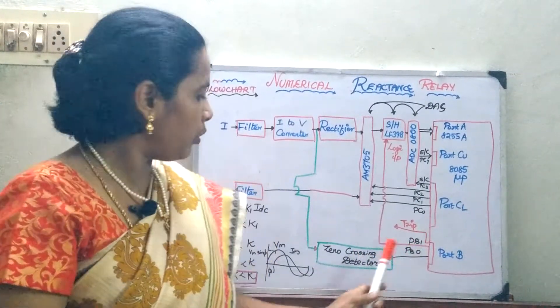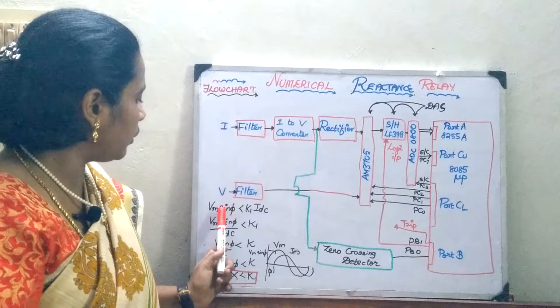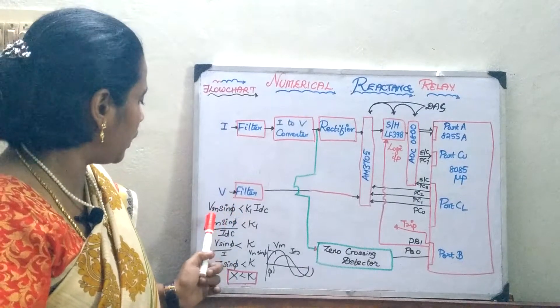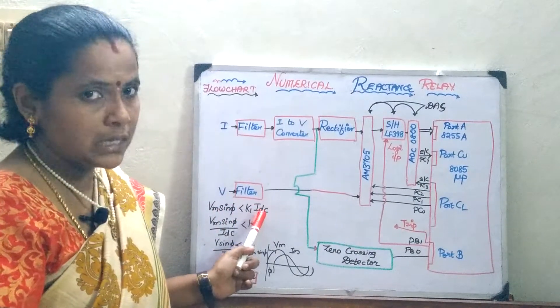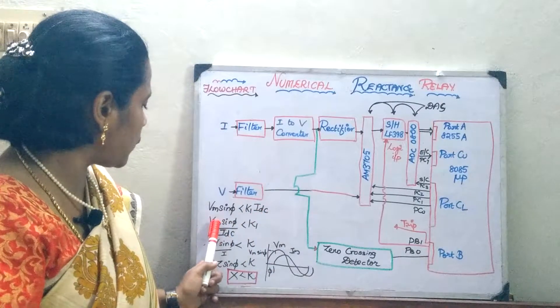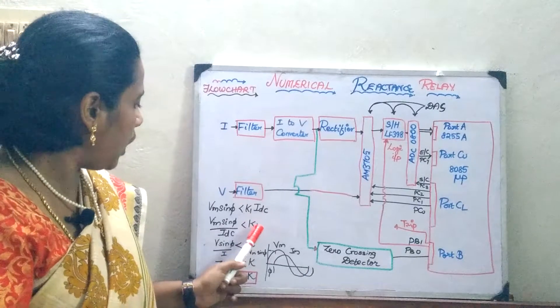Now we will move on to the principle. What is the principle of the reactance relay? You are just going to take the reactance part. So, we are taking your Vm sin phi, you are going to compare it with the IDC. From this, you are getting Vm by IDC into sin phi is less than K1, a constant.